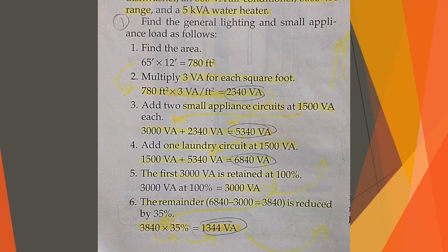Lighting and small appliance requirements are determined similarly to other one or two family residences. The 3 VAs per square foot, 2 small appliance circuits, and 1 laundry circuit rules are used. Add to this the nameplate ratings for motors and the loads for heater, garbage disposal, dishwasher, water heater, clothes dryer, wall-mounted oven, cooking units, and similar appliances. Freestanding ranges, unlike wall-mounted ovens or cooktops, are rated at 80% of their volt amperage up to 10,000 VAs.